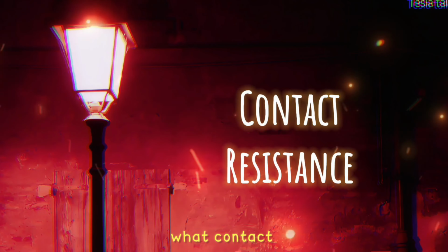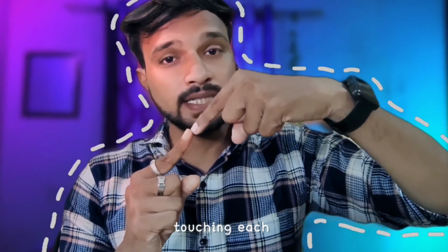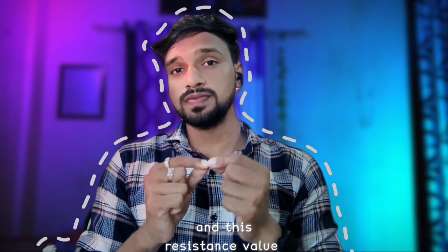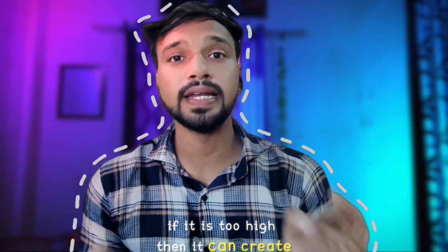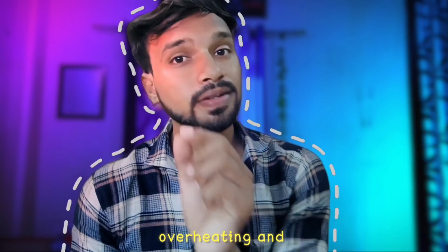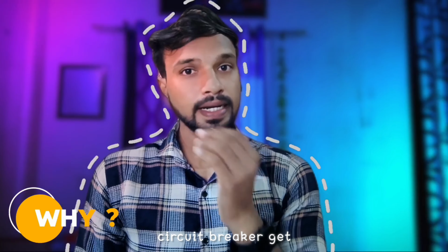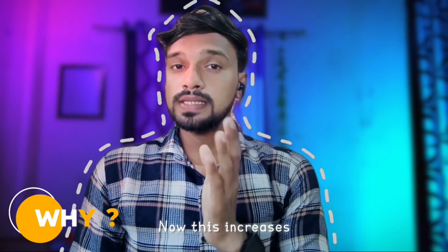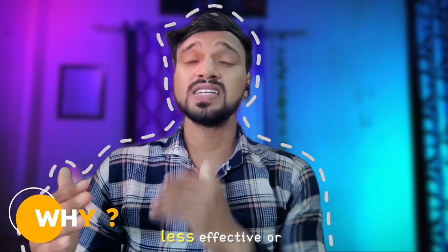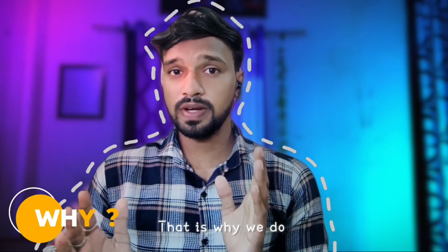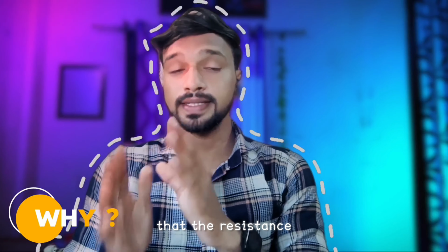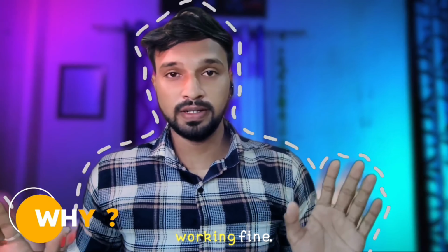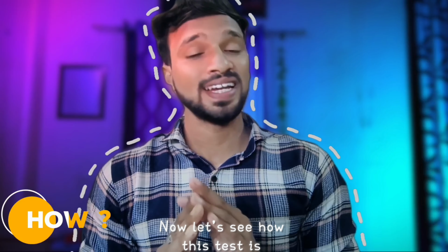Let's talk about what contact resistance is. Imagine you have two metal pieces touching each other, and the point where they touch creates something which is called resistance. And this resistance value should be very low, because if it is too high, then it can create problems like overheating and energy loss. But why is this test so important? Well, over time, the contacts inside a circuit breaker get dirty or can wear out. Now, this increases the resistance, which can make the circuit breaker less effective or even dangerous. That is why we do a contact resistance test, to ensure that the resistance is low and the breaker is working fine.